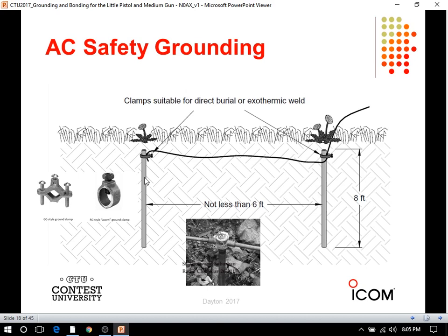When you put in your ground rods, the spec now is two ground rods, not less than 6 feet apart. They typically want you to space them at least as far apart as they are deep in the ground, so if you've got an 8-foot ground rod, you put them 8 feet across.